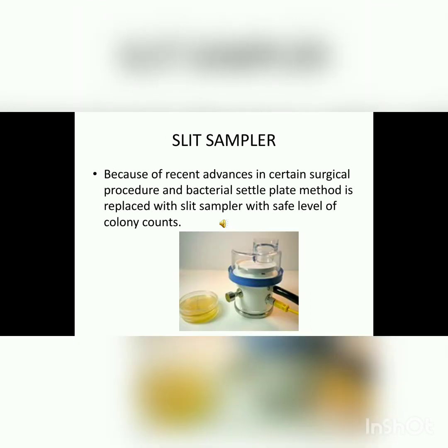For the result and interpretation, plates should be incubated under optimum conditions for 24 hours. Aerobic cultures on non-selective medium should not exceed 35 colony forming units of bacteria and fungi per cubic meter for a conventional theater, and one colony forming unit for an ultra clean theater.